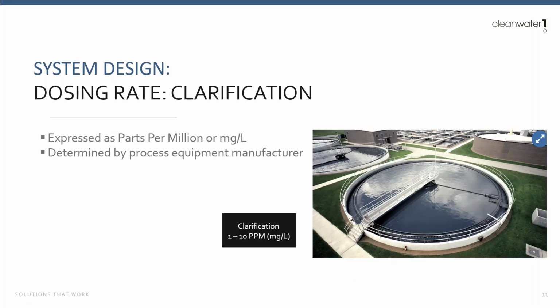The dosing rate for clarification and filtration is much more tricky. It's expressed as parts per million or milligrams per liter. And this generally needs to be determined by process equipment manufacturer and bench testing. You can see we have a general guideline of 1 to 10 parts per million, but that's actually a really wide range, right? So we can kind of have an estimate in there to begin with, but again, it's really important to nail that down further along in design.